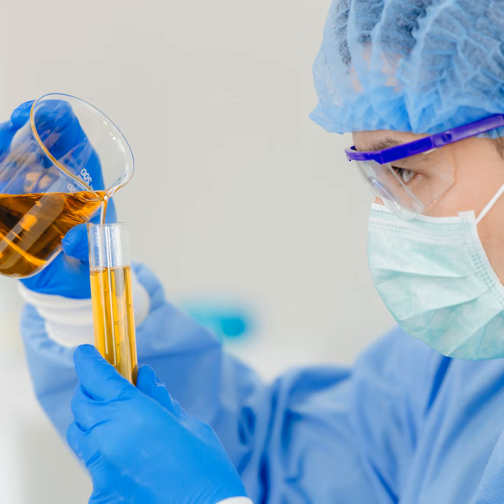While all of this technology is fascinating, there's one point that stands above everything else: the quality of the oil sample itself. Even the most advanced laboratory equipment cannot produce meaningful results if the sample isn't representative of the system. The way the sample is collected has a greater influence on the final cleanliness result than almost anything that happens afterwards. If contamination is introduced during sampling, or if the sample doesn't accurately represent the operating condition of the machine, the reported cleanliness code may not reflect the true condition of the hydraulic system. In other words, good data begins with good sampling. It's a simple idea, but one that's easy to overlook.